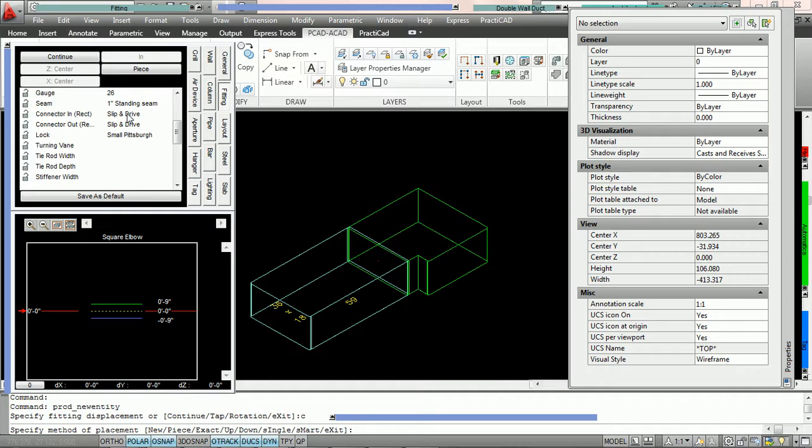That will always be the choice when we're taking the width of one fitting and attaching it to the width of another fitting. And we always read in PractiCAD the width of elbows as the cheek parameter. So this parameter here is the width of the elbow. The throat parameter is the depth. So since we're attaching the width of the elbow to the width of the rectangular duct, and they're attached right here, we're using the compatible parameters.